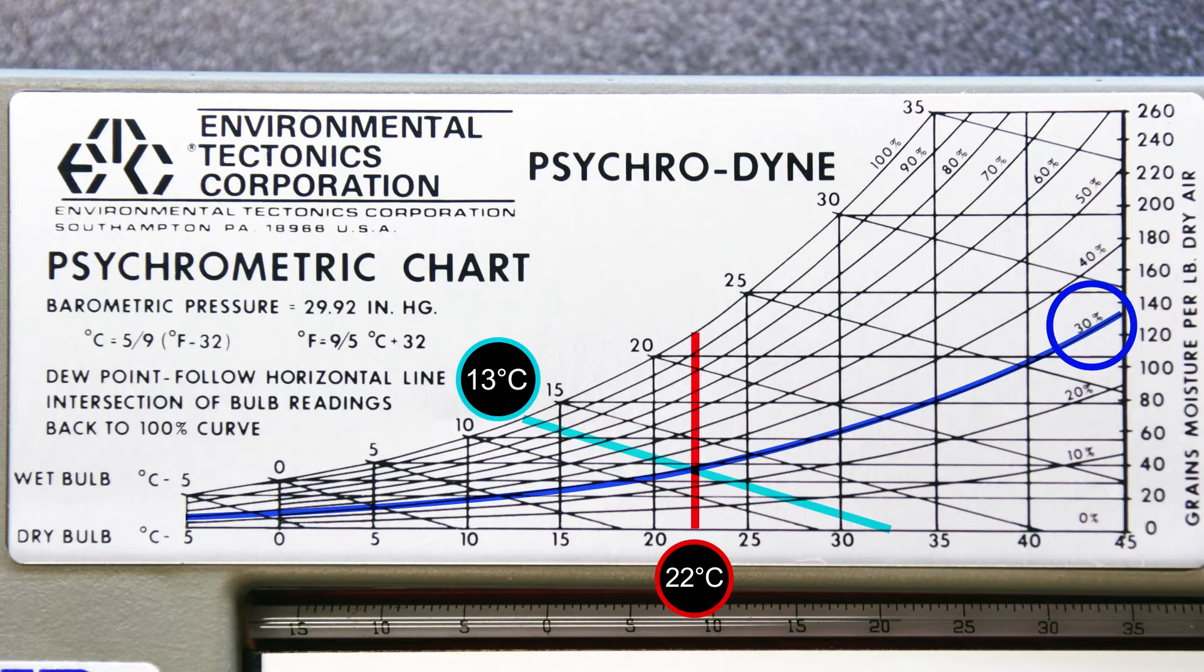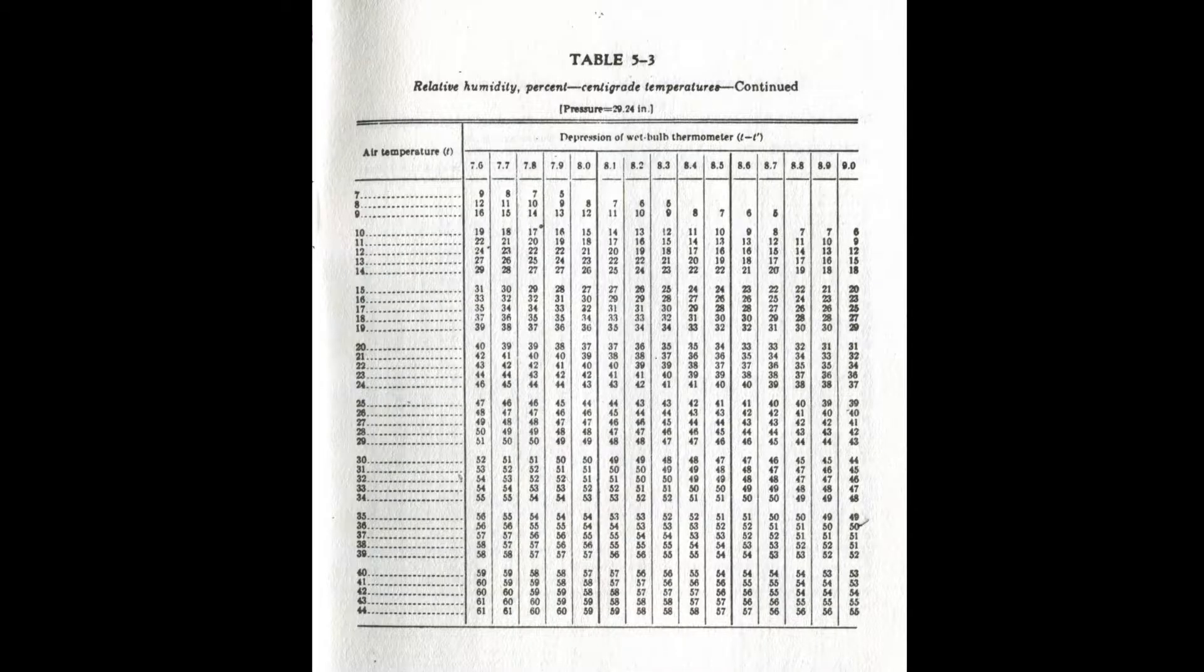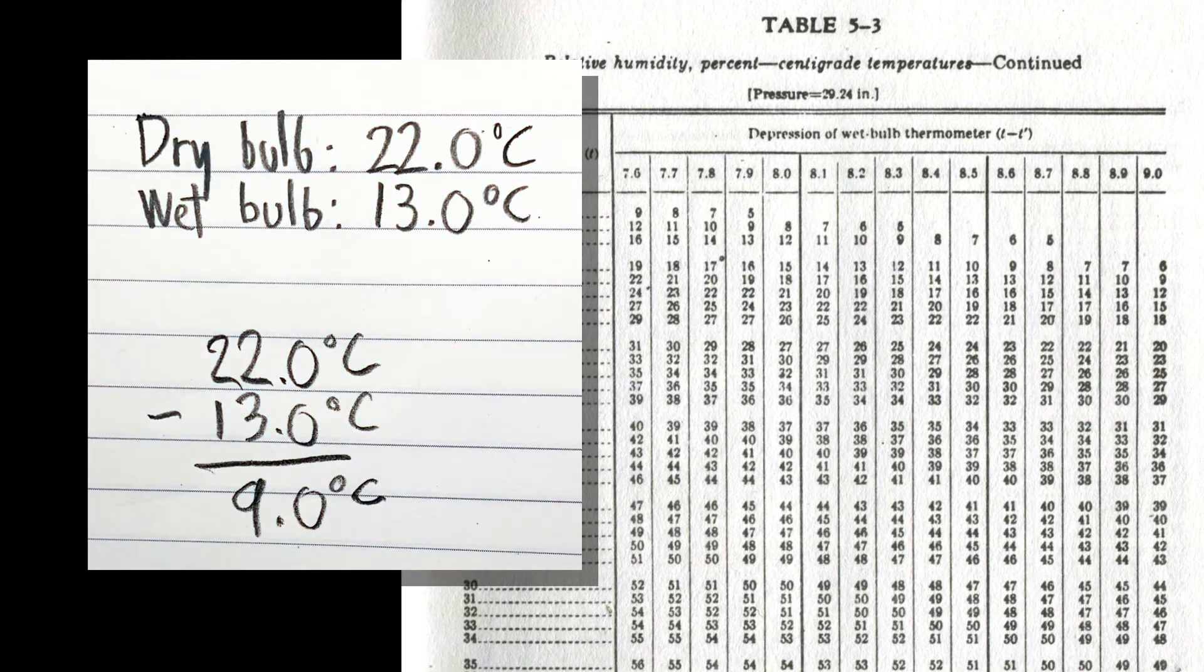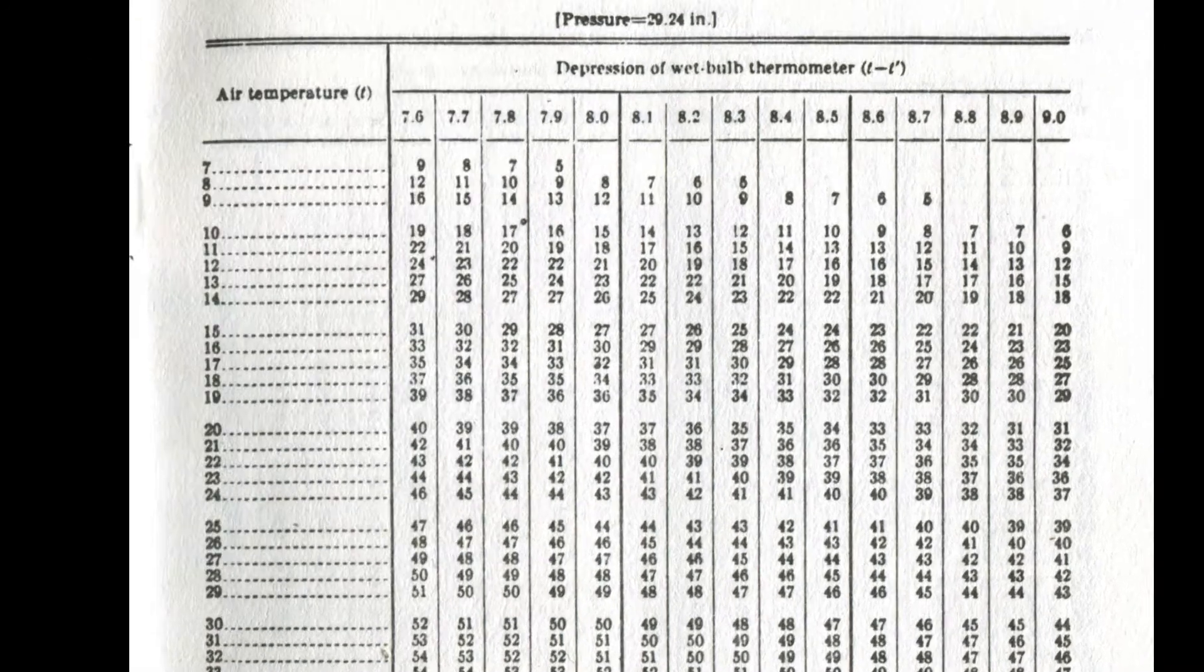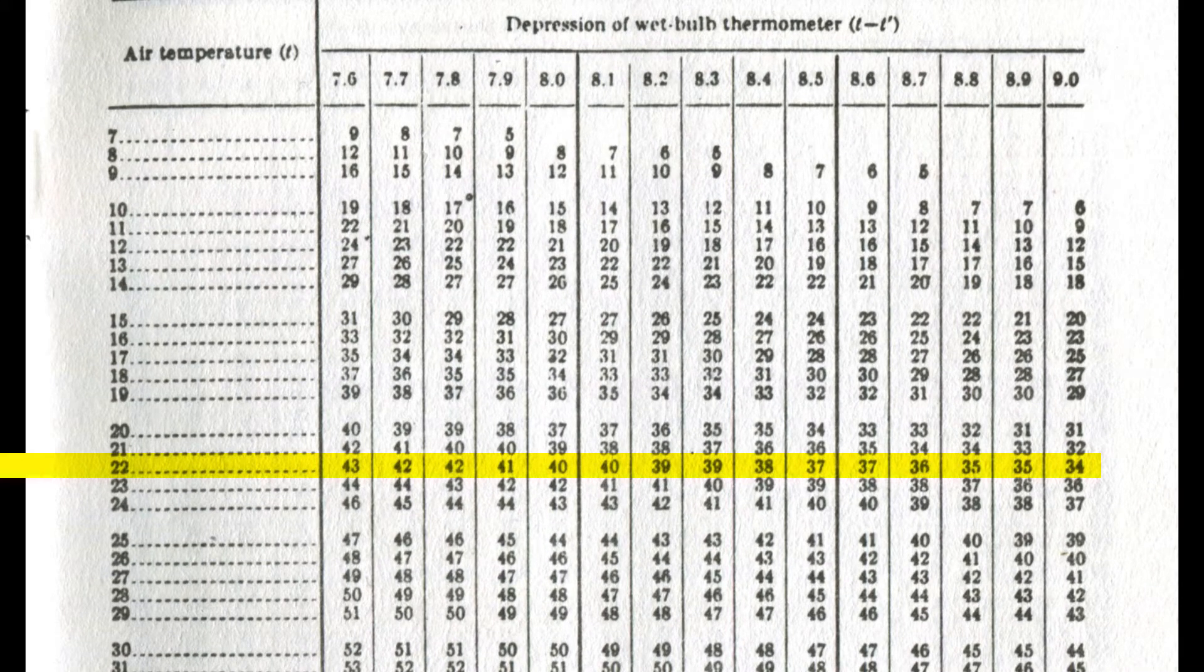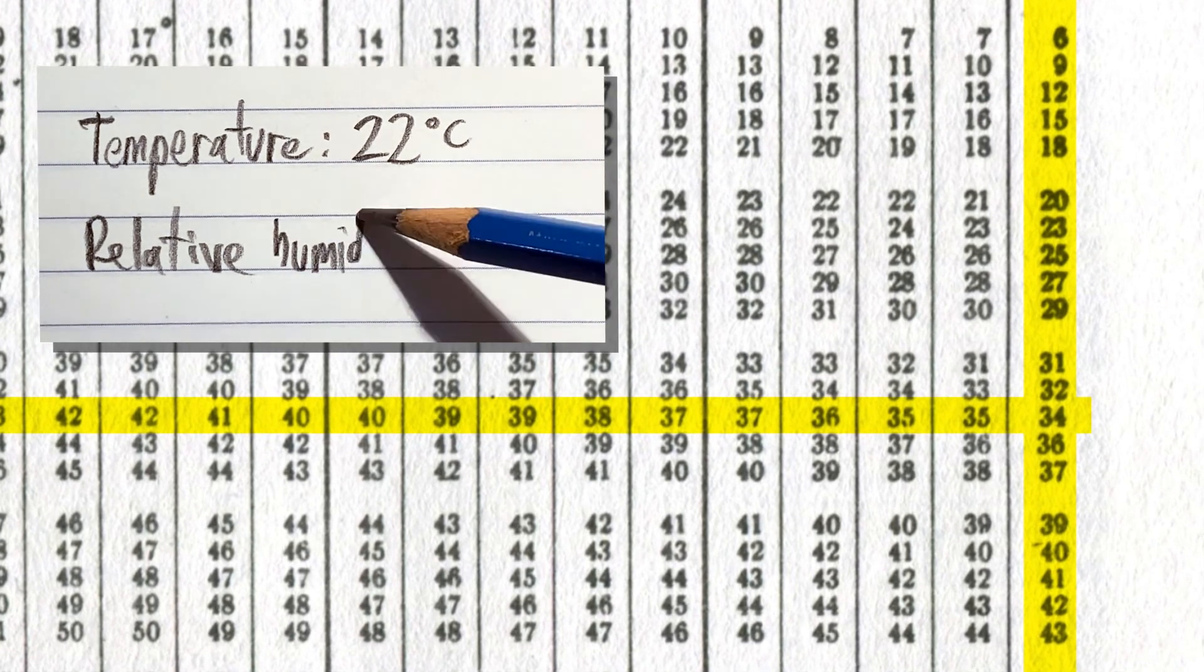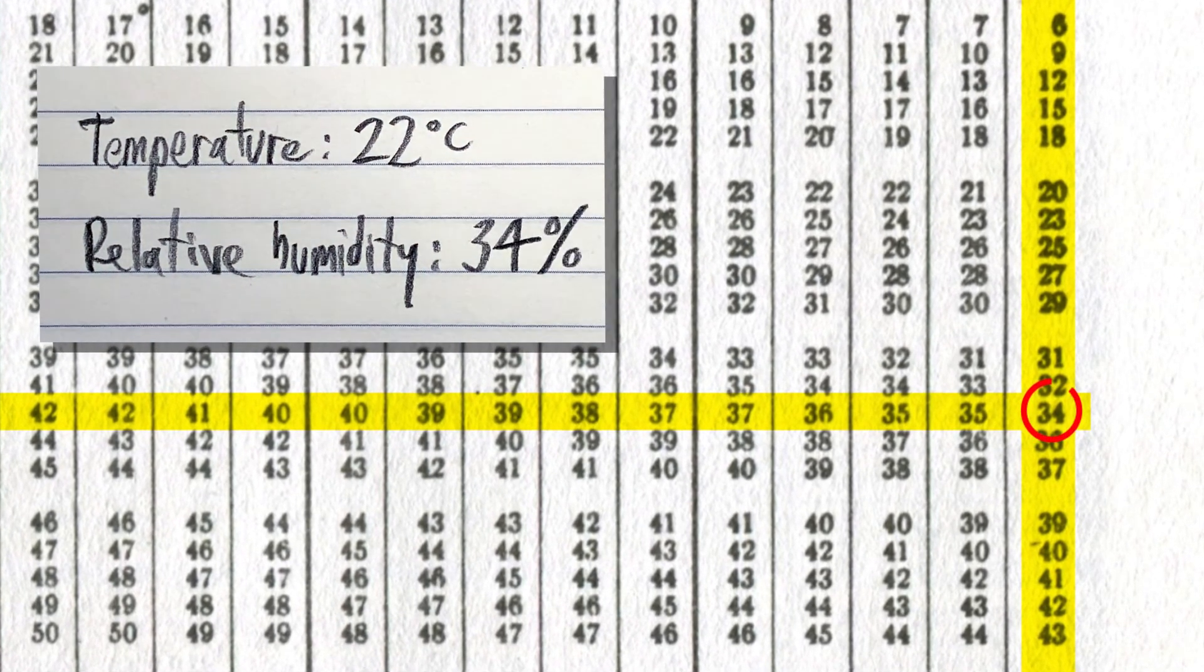For a more accurate relative humidity reading, use the tables in the instrument's manual. First, subtract the wet bulb temperature from the dry bulb temperature to calculate the difference. Next, find the air temperature row that corresponds to the dry bulb temperature value. Find the depression of wet bulb thermometer column that corresponds to the calculated difference between the dry bulb and wet bulb thermometers. The value where these two intersect is the relative humidity of the space.